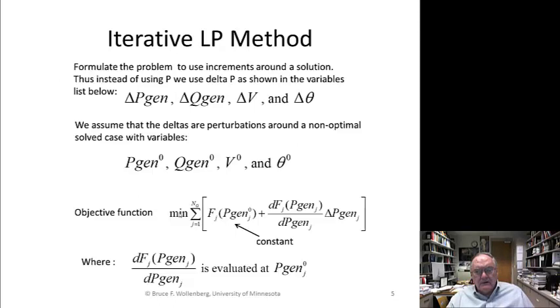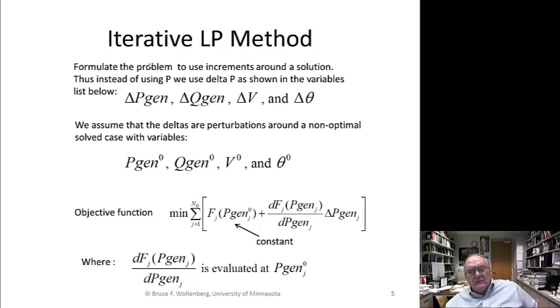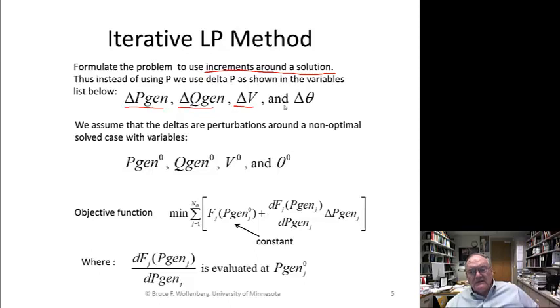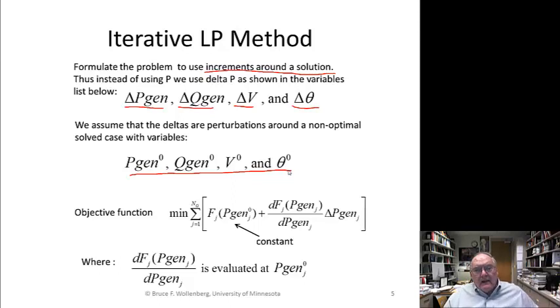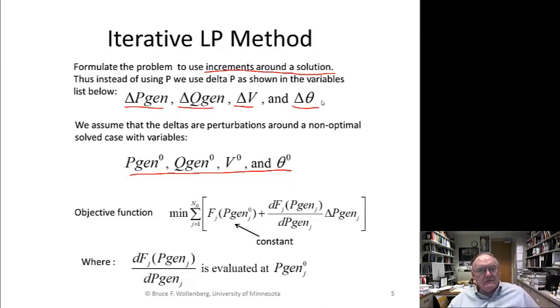To do iterative LP, we change the problem and say it really uses increments around a solution. So instead of pgen, it's delta pgen, delta qgen, delta V, delta theta. We assume that the deltas are perturbations around some solved case, and that solved case keeps getting updated during the process. We start with a solved case, do an LP around it with these delta variables, it moves them in the optimal direction obeying all constraints, then we get a new solution and do new perturbations around that.